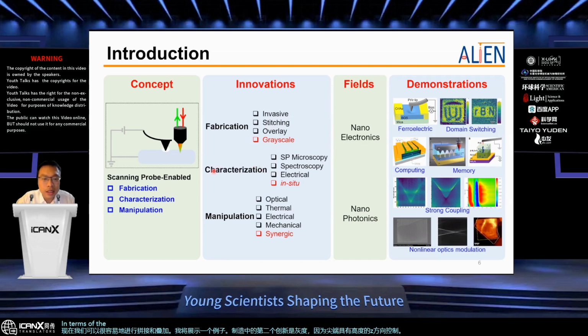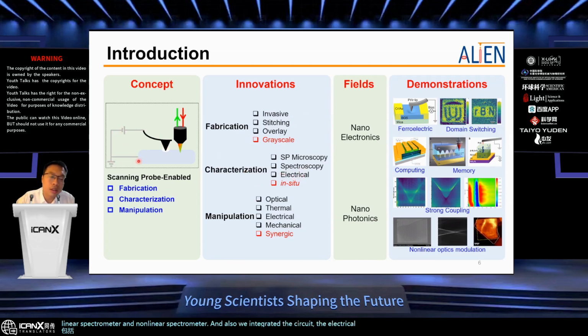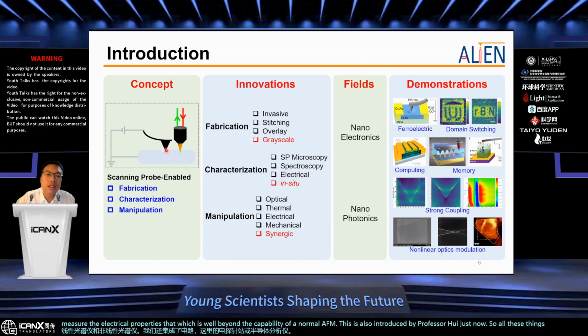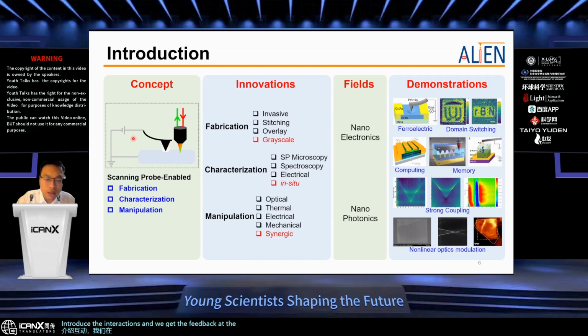The second innovation is the characterization, because the tip, again being a scanning probe technology, allows us to do scanning probe based microscopy, for example topography or C-AFM, just like Professor Hui introduced. And by introducing the laser system, we are able to measure spectra, including linear and nonlinear spectroscopy. We also integrated the electrical probe station, or the semiconductor analyzer, to measure electrical properties, which is well beyond the capability of normal AFM. This was also introduced by Professor Hui just now. So all these things can be done at the same time, which means we introduce the interactions and we get the feedback at the same time in electrical, optical, and scanning probe-based microscopy.